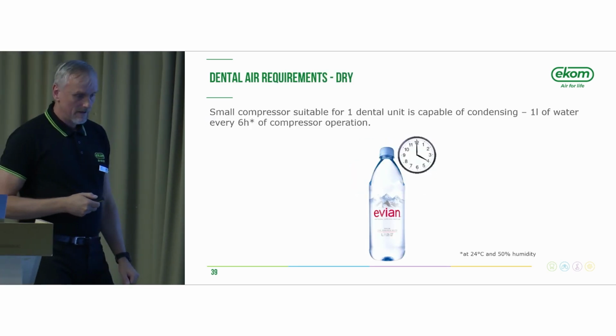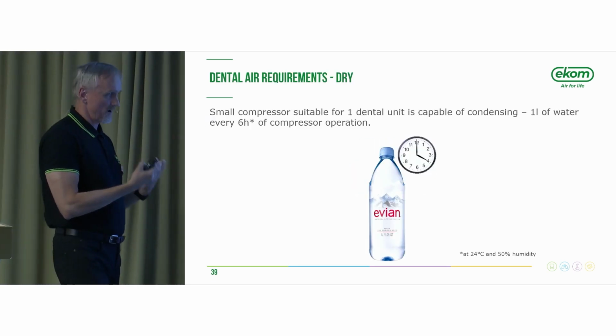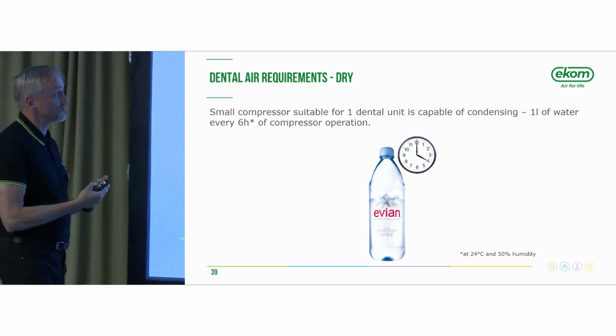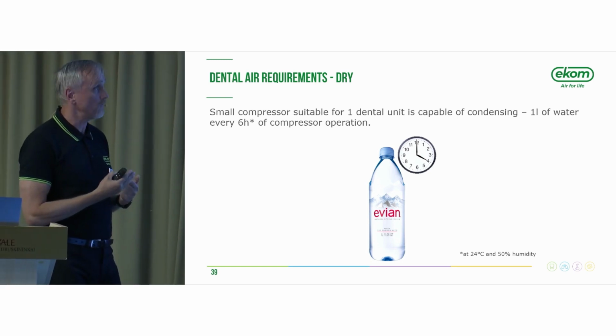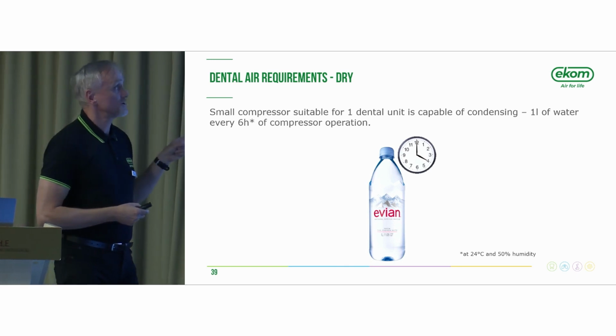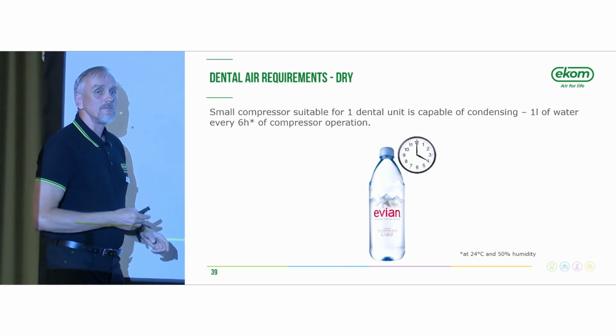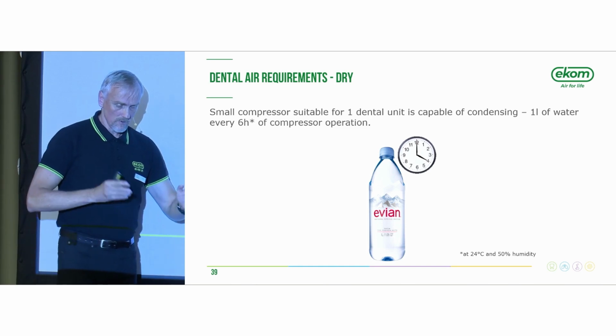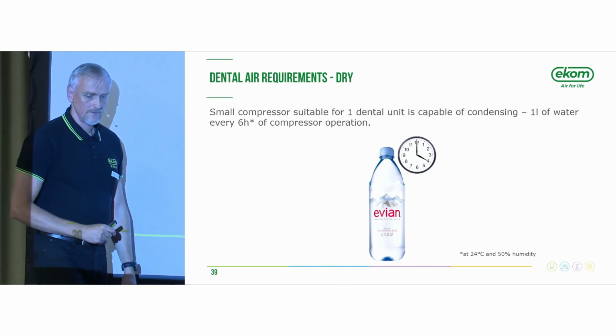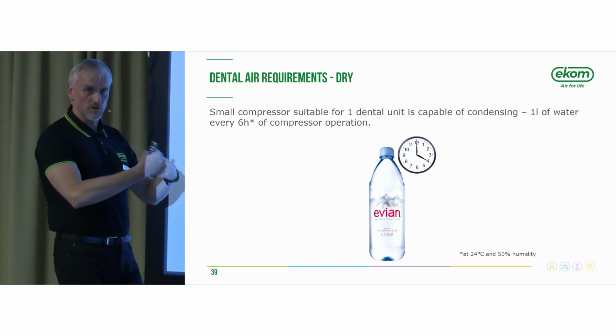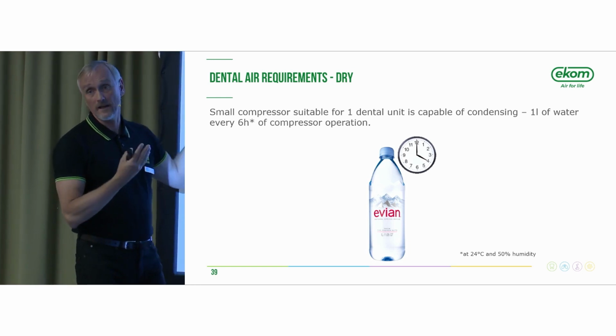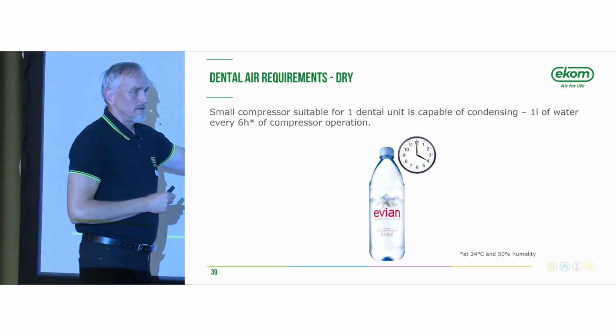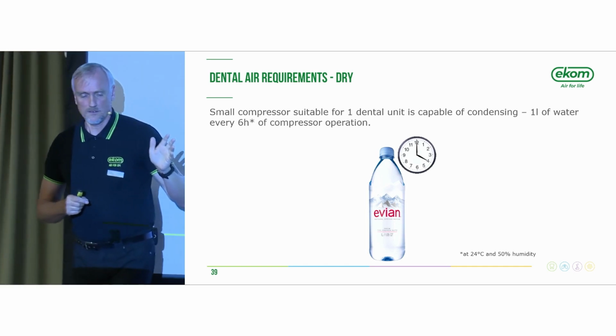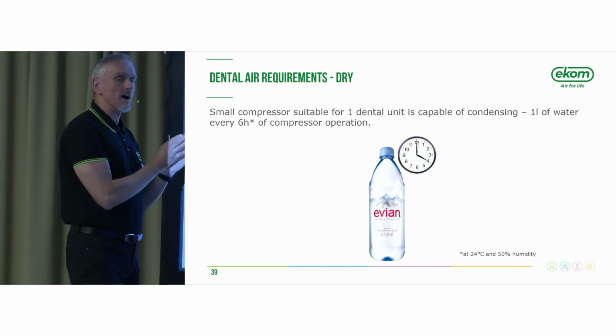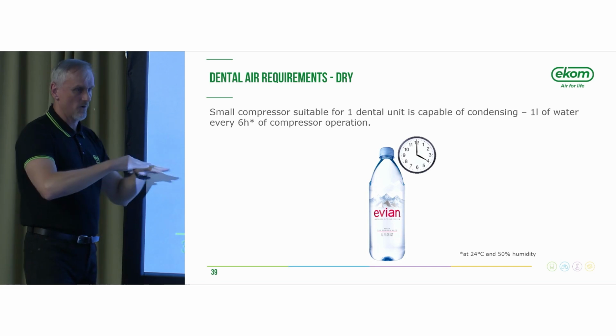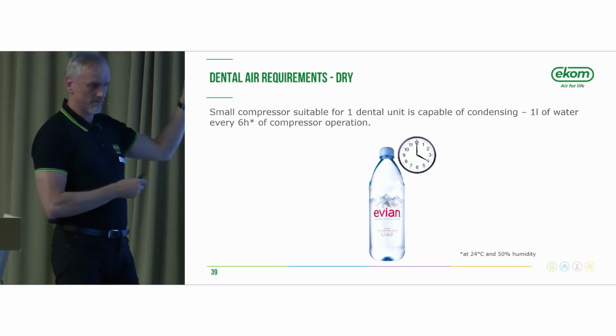One dental chair, actually with a compressor suitable for one dental chair, is capable of condensing 1 liter of water every 6 hours of compressor operation - I mean pure operating time of the compressor. Of course, since the compressor doesn't work continuously, this may take maybe a day. Normally a dentist's compressor works around 3 hours a day, which is typical, so it's roughly a 2-day situation.